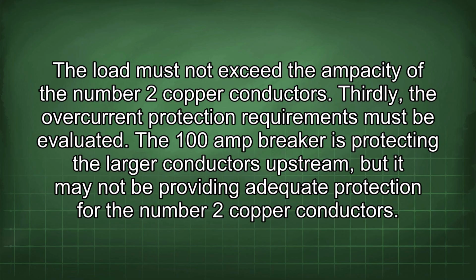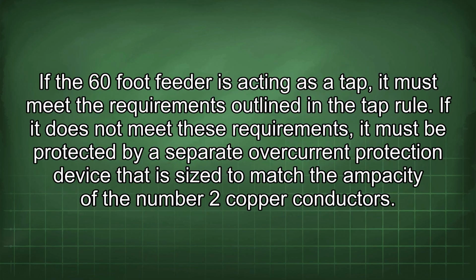Thirdly, the overcurrent protection requirements must be evaluated. The 100-amp breaker is protecting the larger conductors upstream, but it may not be providing adequate protection for the number 2 copper conductors. If the 60-foot feeder is acting as a tap, it must meet the requirements outlined in the tap rule. If it does not meet these requirements, it must be protected by a separate overcurrent protection device that is sized to match the ampacity of the number 2 copper conductors.